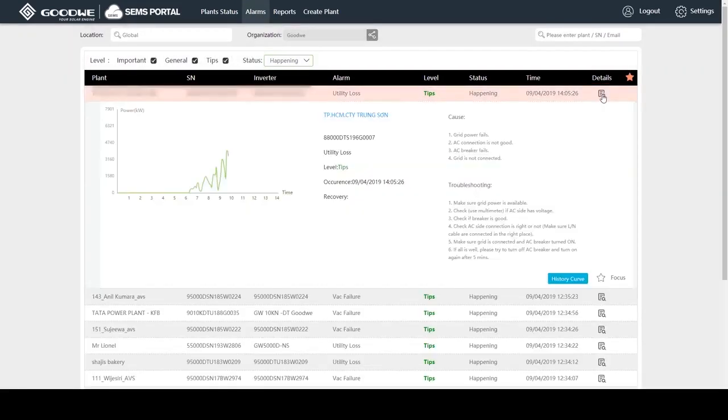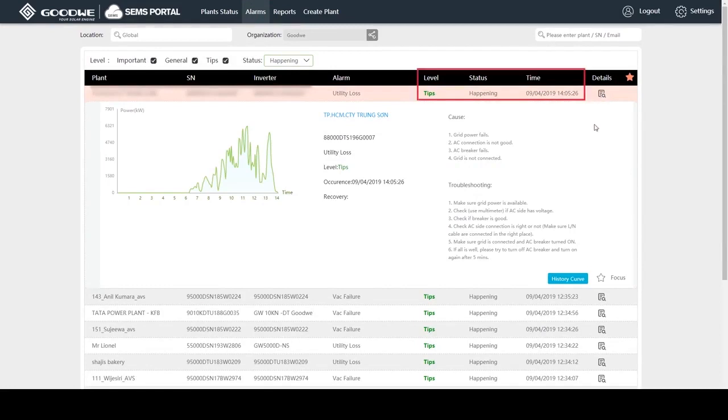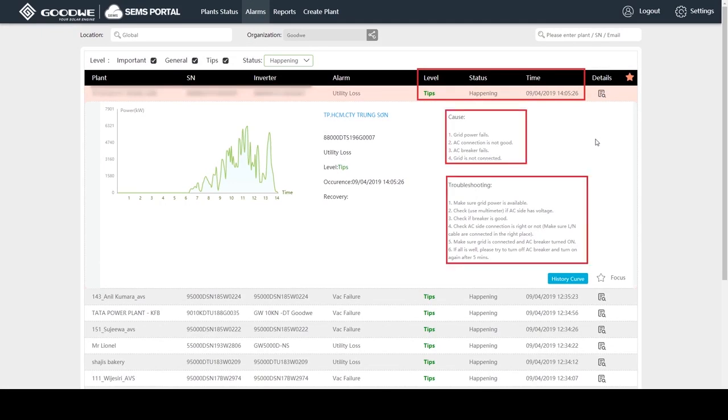When I click on details, we can find which inverter in which plant has what error during what time. Plus, these errors are arranged according to the warning level and status. We can also find analysis of the occurrence of such error, and get troubleshooting advice and more details as well.